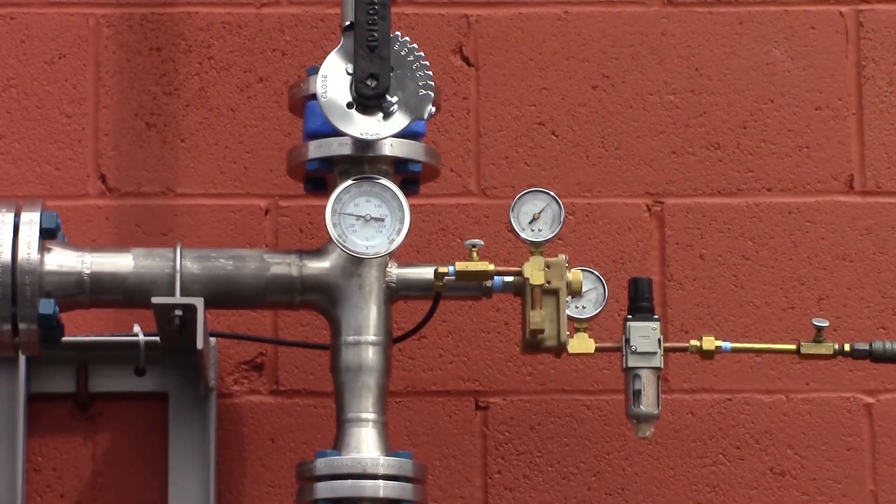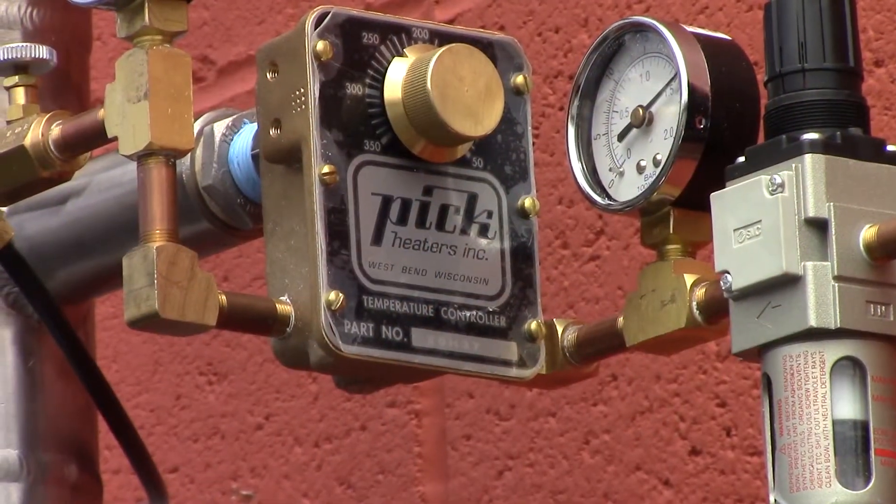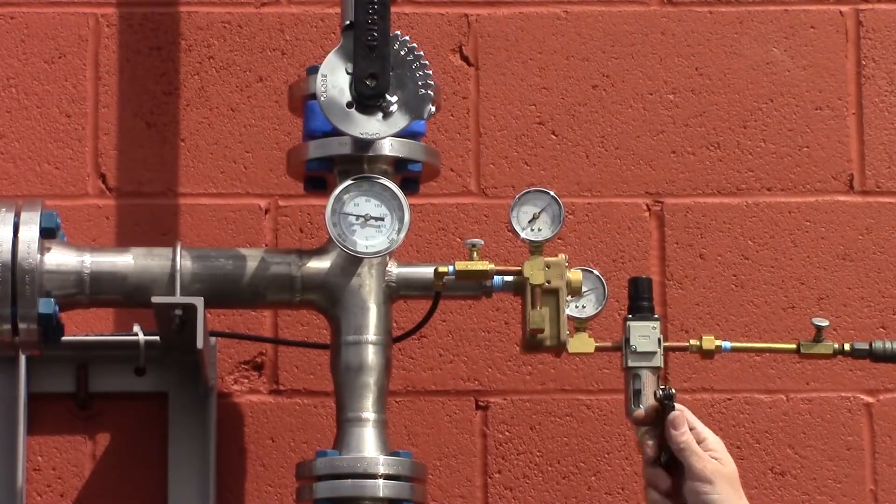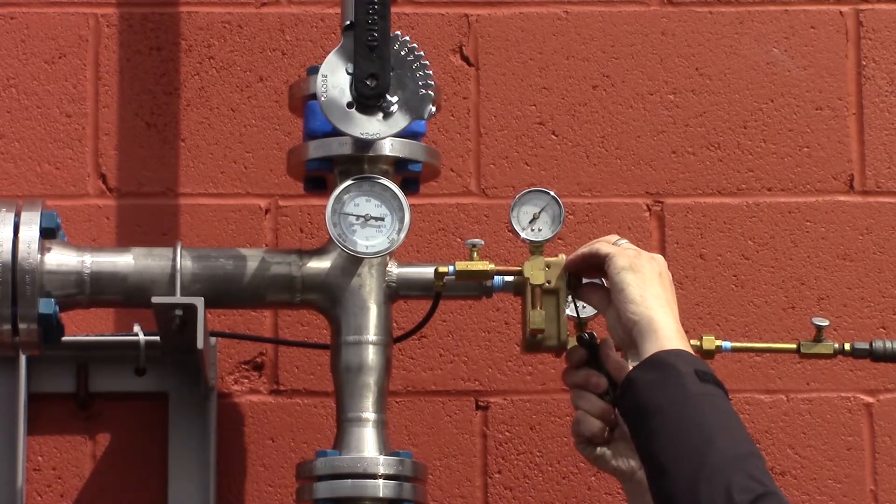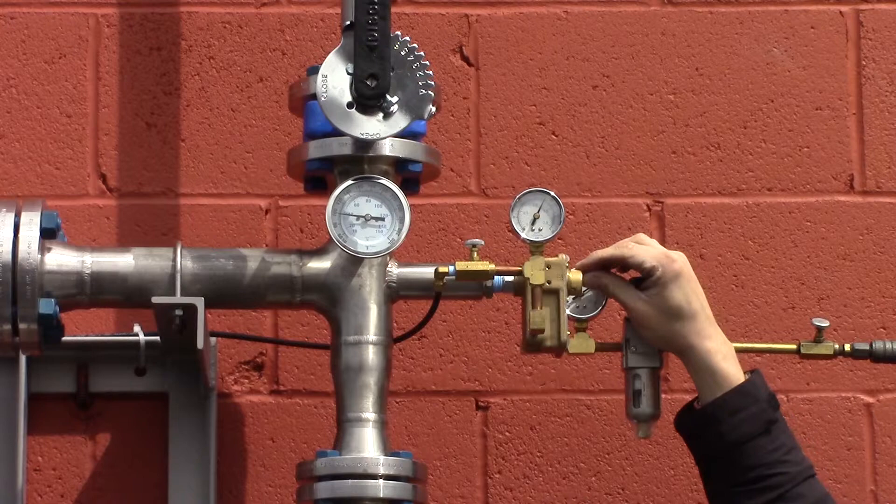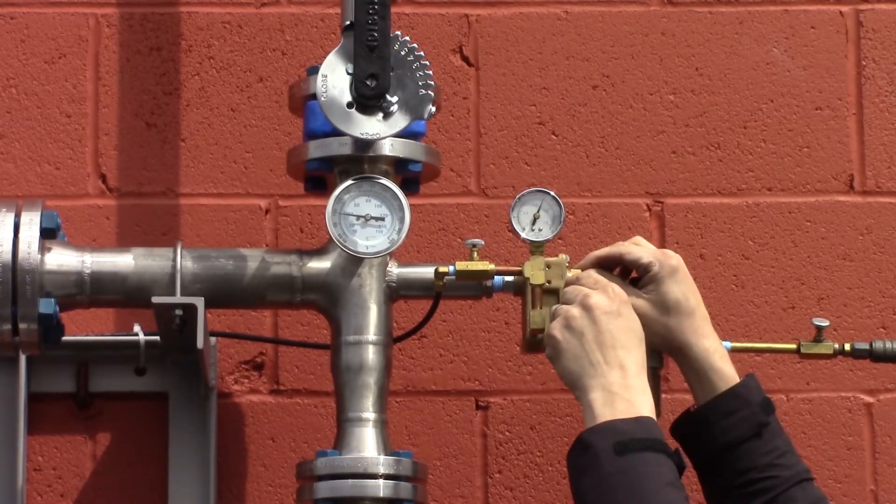The notch in the knob may not necessarily be aligned with the dial thermometer at this point. Next, use a 3/32 inch hex key wrench to loosen the set screw on the knob. Now reposition the knob so the notch aligns with the same temperature on the dial thermometer.